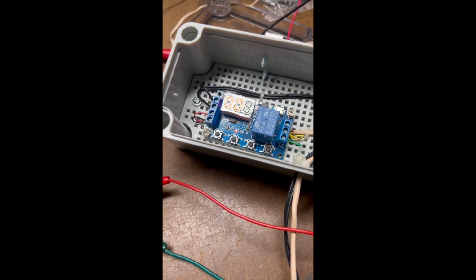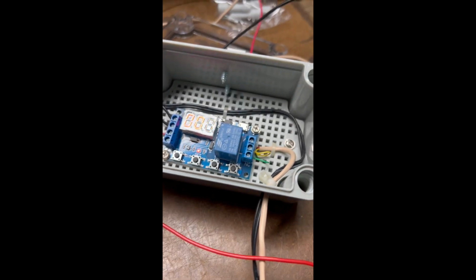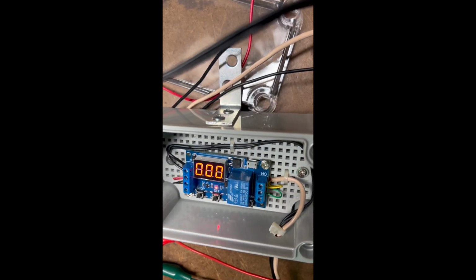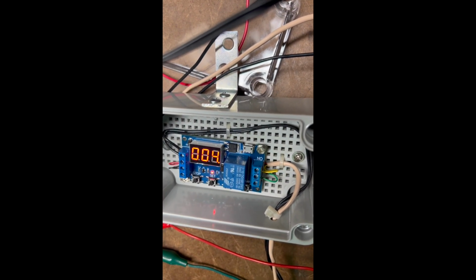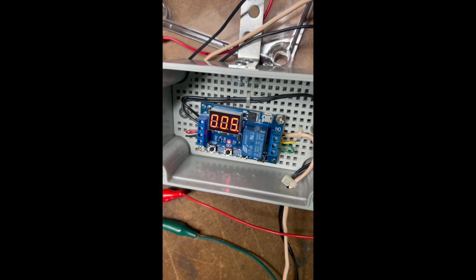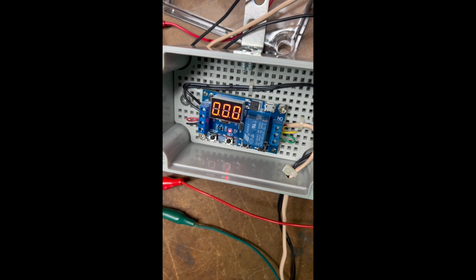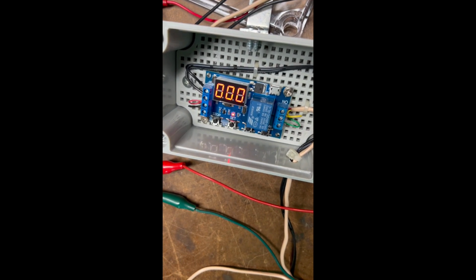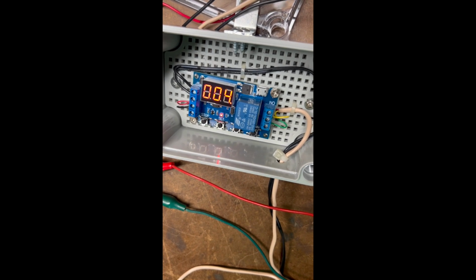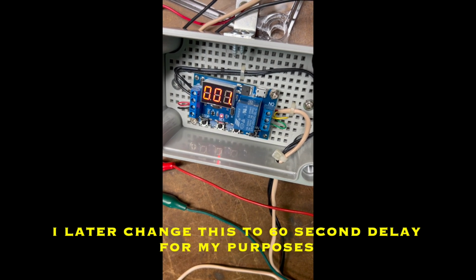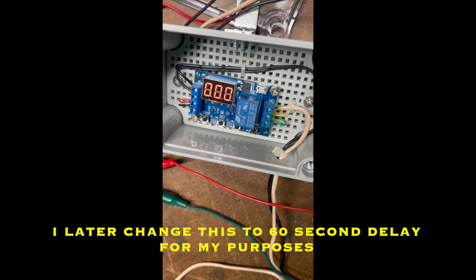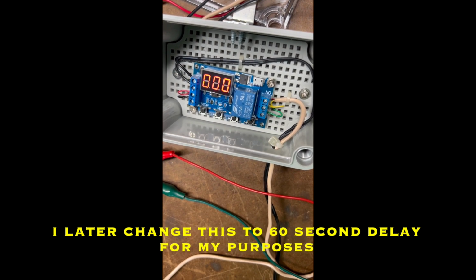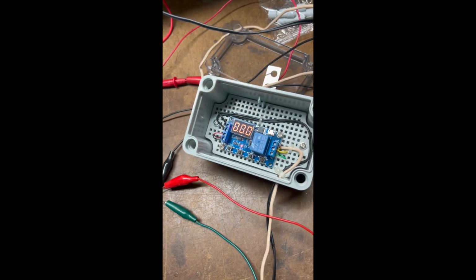But during the countdown time, I can continue to apply and unapply that, and it will keep resetting the timer, which is good. So if we get power fluctuations, every time that power comes back, it resets the timer when I disconnect it. Now, we go to this state here. So now we're in alarm condition again. Power comes back. We're in a non-alarm position. So this is the basic principle.